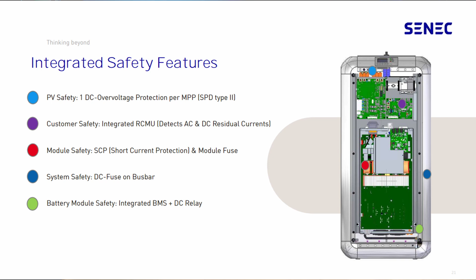We have an integrated RCMU, which detects AC and DC residual currents, a huge benefit for customer safety. The system monitors AC and DC residual currents all the time, so there's no need for a Type B RCD on the AC input port because it's already monitoring that - which is a plus. There's also a system fuse on the bus bar, battery module safety, an integrated battery management system, and as a fallback, a DC relay which can disconnect.